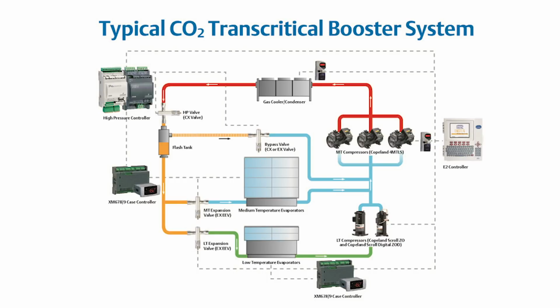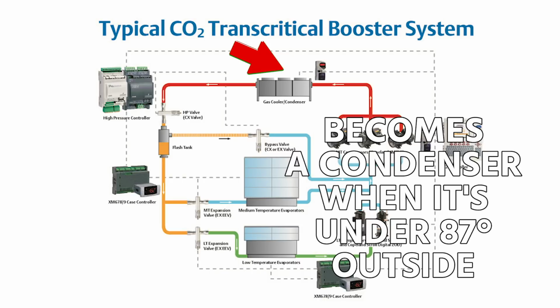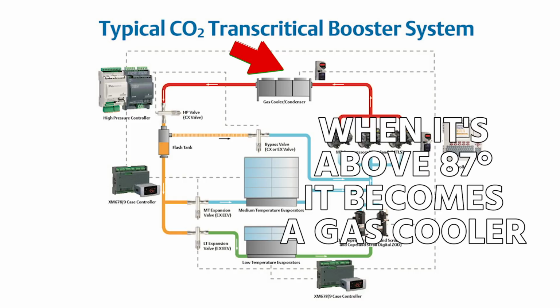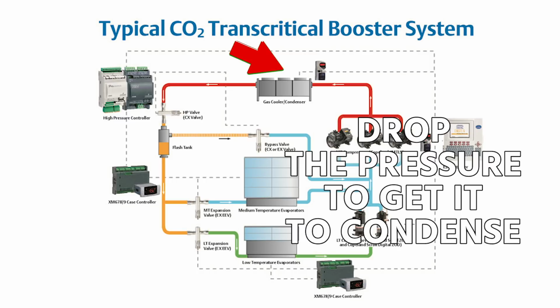So when we're working in that transcritical zone, you'll hear Kevin talk about a gas cooler, and a gas cooler is essentially what we would normally call a condenser, and in fact does become a condenser when it's under 87 degrees outside, so it functions as a condenser. But then when it gets above 87, it's no longer condensing, it's now functioning as a gas cooler, and then we have to drop the pressure in order to get it to condense. So there's some interesting things about CO2.